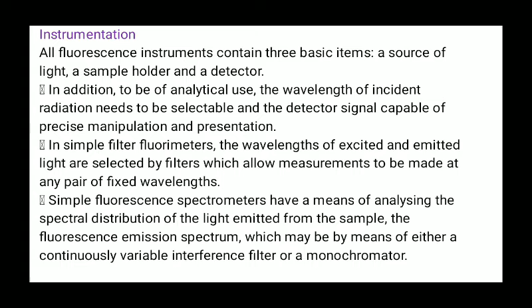So simple fluorescence spectrometers have a means of analyzing the spectral distribution of the light emitted from the sample, that is, the fluorescence emission spectrum, by means of either a continuously variable interference filter or a monochromator. Okay, so that is about the simple fluorescence spectroscopy, right? But in a more sophisticated instrument, monochromators are provided for both the selection of exciting light and the analysis of sample emission.